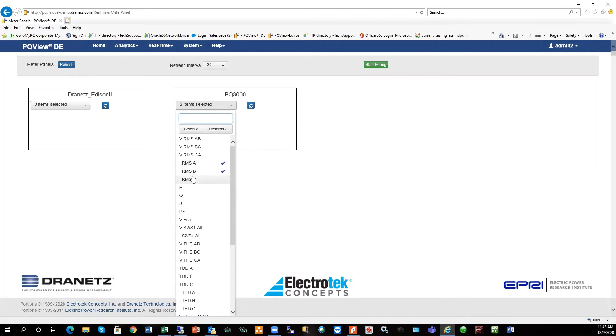We can go in and keep it simple - we'll select voltage, and maybe on our PQ3000 that Ross mentioned earlier, we'll select current. We then choose how often we want to update - we can say 30 seconds, or something less, let's say every 10 seconds, and then you begin to poll. Every 10 seconds it'll provide real-time information. So in this example, for this meter, for voltage, we have a 208/120 service, and we're monitoring just current in the PQ3K. You can have as many meters as your display will allow for viewing real-time data. That's an example of real-time.